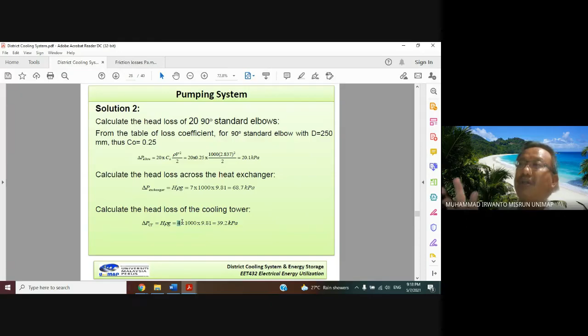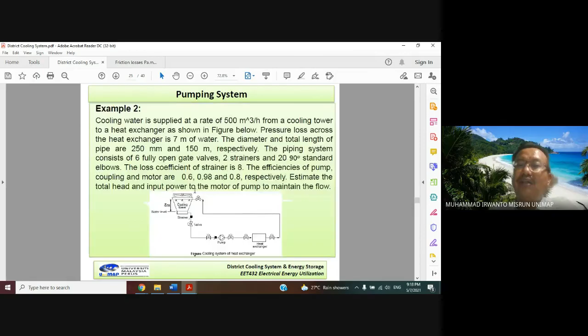We have obtained all the friction losses: the pipe, the fittings, the exchanger, and also the cooling tower. Now delta P total is equal to the friction of the pipe plus all the friction of the fittings, exchanger and cooling tower. Lastly, we have obtained delta P total as 226.85 kPa, following this formulation.